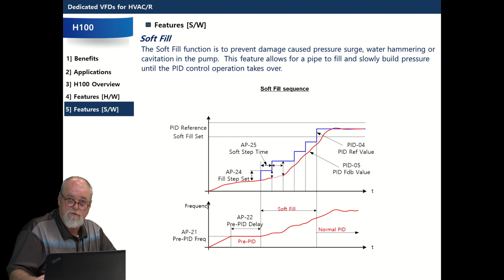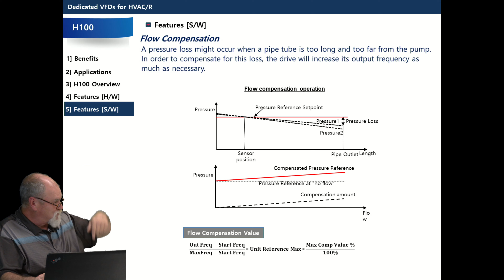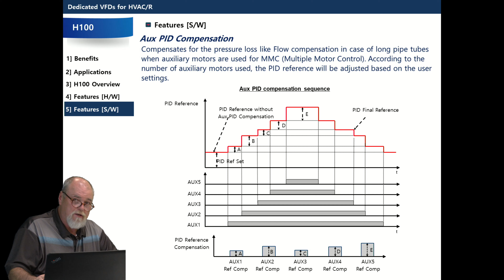Flow compensation: say you require X amount of pressure at the end of a long run, and your pressure transducer is at the beginning of the pipe section. We can compensate to boost the power, boost the voltage or speed to compensate for the pressure drop. That's more for larger buildings, say like in New York, where it's 50 floors up, and you put in a pressure transducer right at the pump, which is crazy, but you don't want to run 50 floors up just to bring your pressure transducer down. You can compensate for that. We have additional things we can do on the PID loop for compensation to offset some issues with bends or some losses.